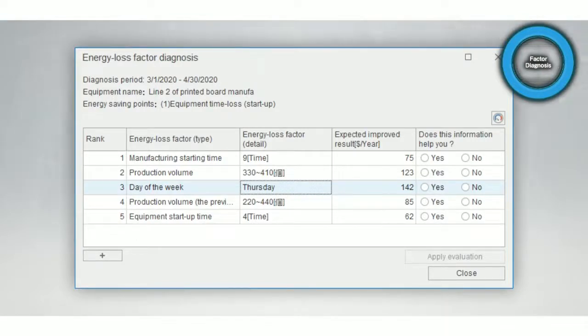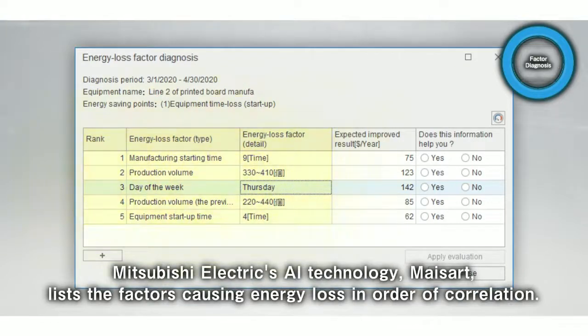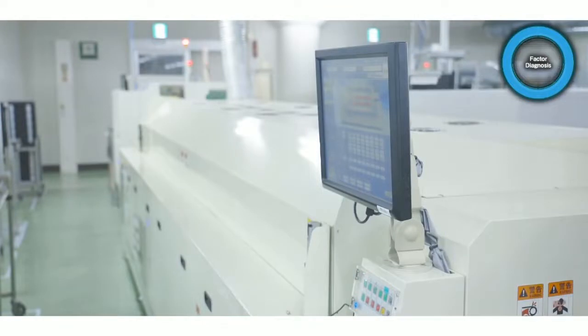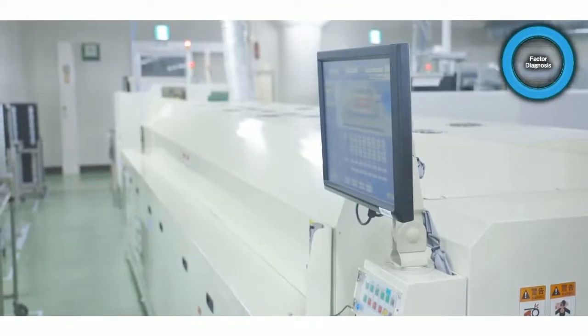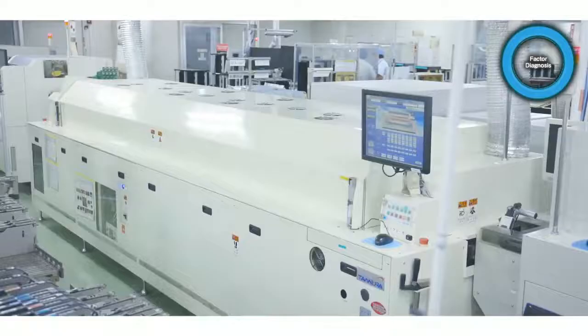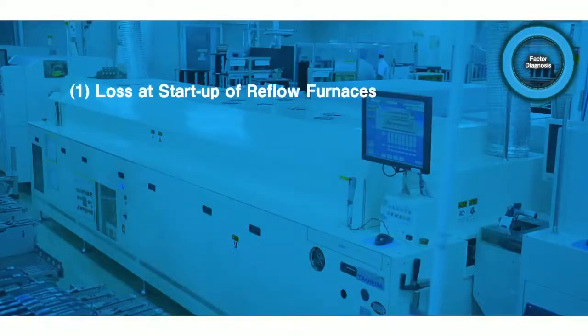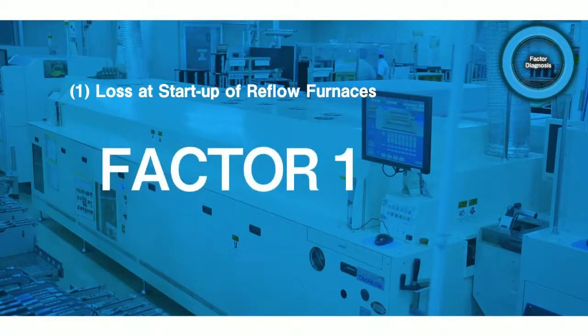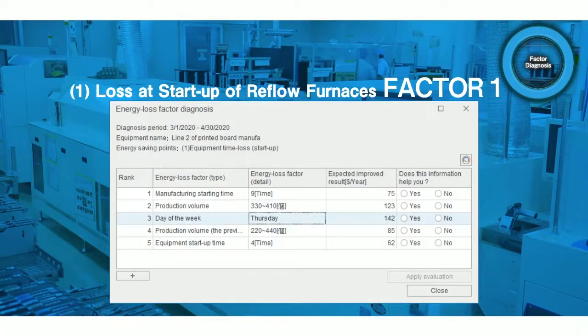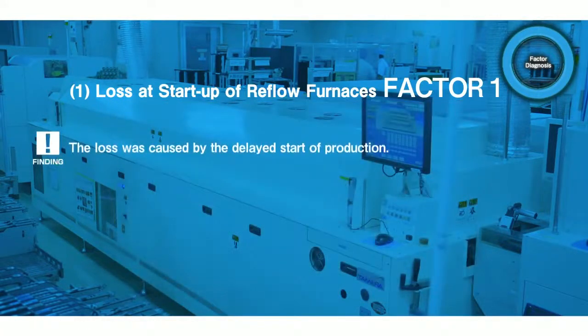Based on information such as date and time, production, and more, the factors causing energy loss are listed in order of correlation and visualized with the expected improvement effect. By utilizing this function, two factors causing the loss were identified. The most critical factor suggested as the cause of loss was the production start time between 9 and 10 a.m. It was assumed that there was loss when the production start time was late compared to the startup time of the reflow furnaces.